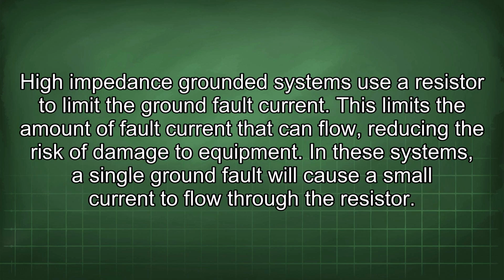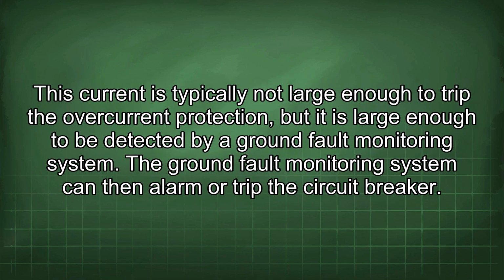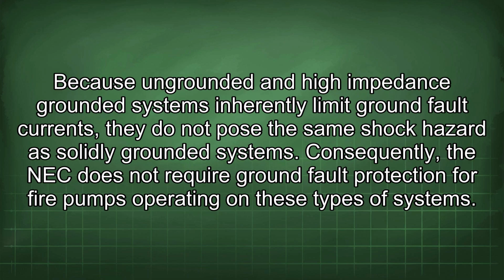High impedance grounded systems use a resistor to limit the ground fault current. This limits the amount of fault current that can flow, reducing the risk of damage to equipment. In these systems, a single ground fault will cause a small current to flow through the resistor. This current is typically not large enough to trip the overcurrent protection, but it is large enough to be detected by a ground fault monitoring system. The ground fault monitoring system can then alarm or trip the circuit breaker. Because ungrounded and high impedance grounded systems inherently limit ground fault currents, they do not pose the same shock hazard as solidly grounded systems.